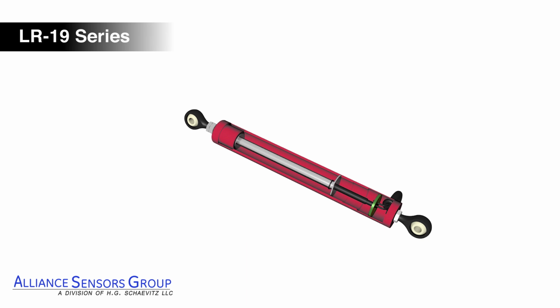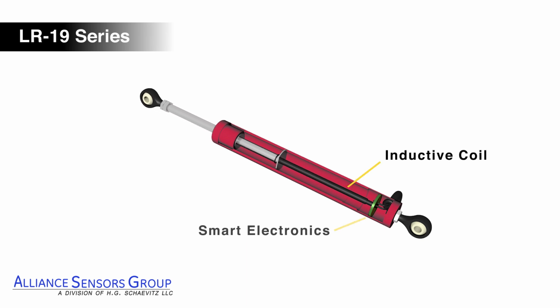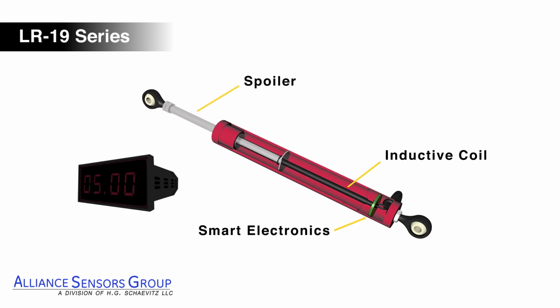LVIT technology consists of a high-resolution inductive sensing coil element coupled to built-in smart electronics. A conductive tube, referred to as a spoiler, travels over the coil element, changing the inductance. The smart electronics then generate an analog output signal proportional to the change in stroke.